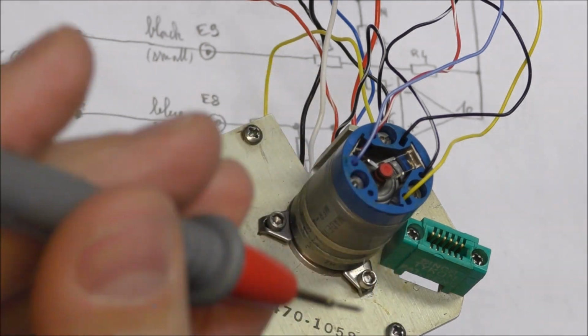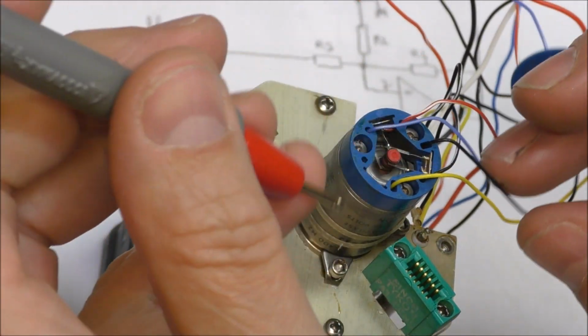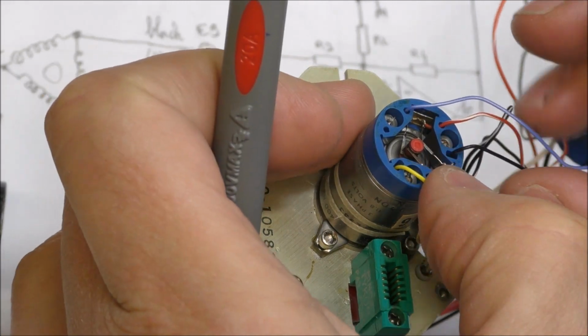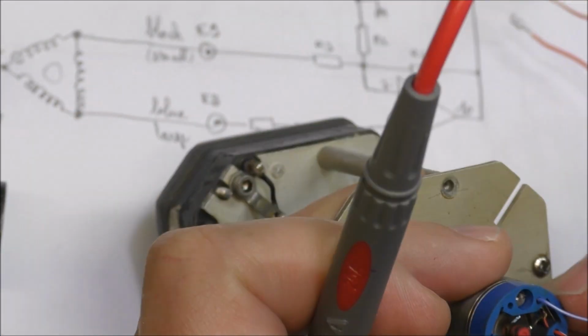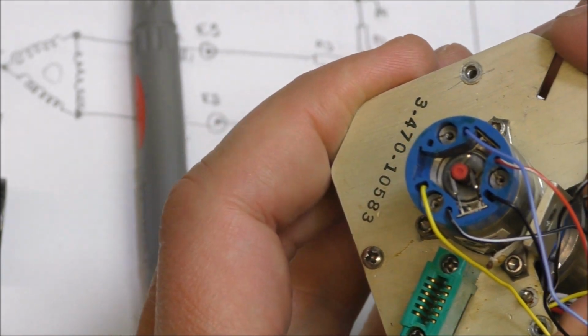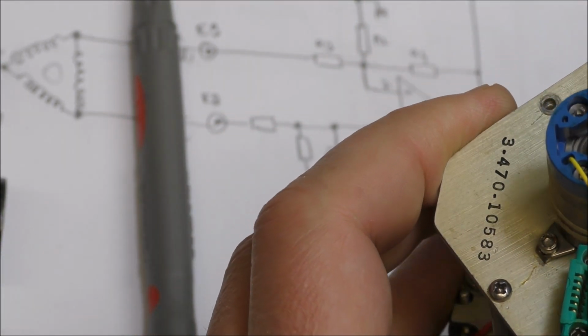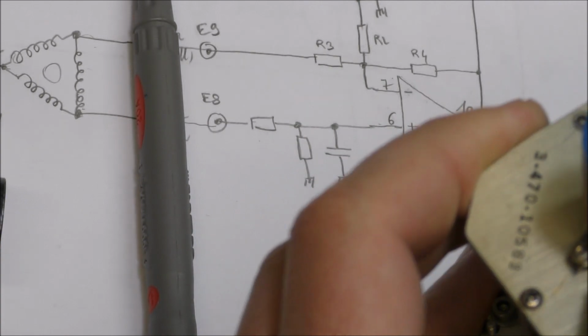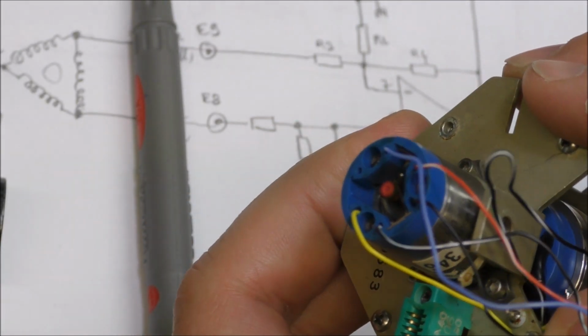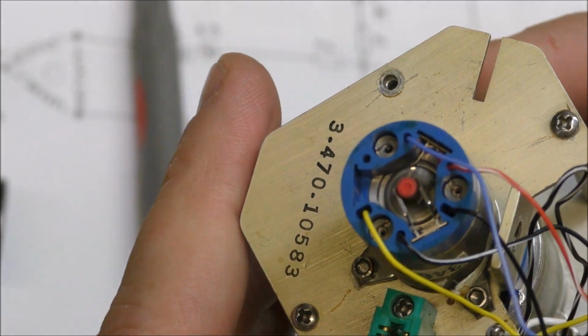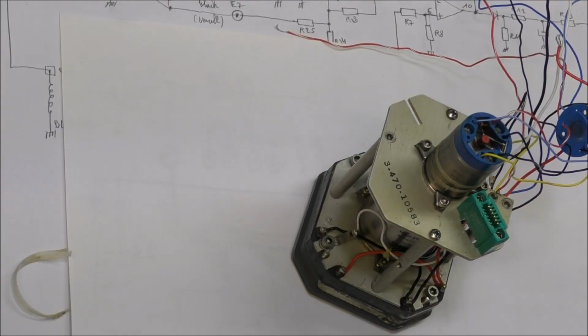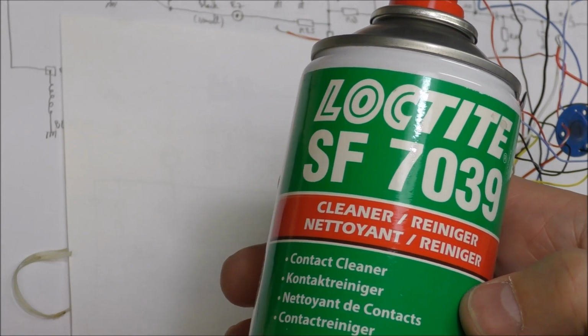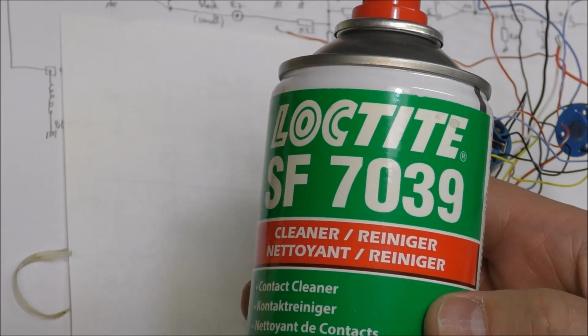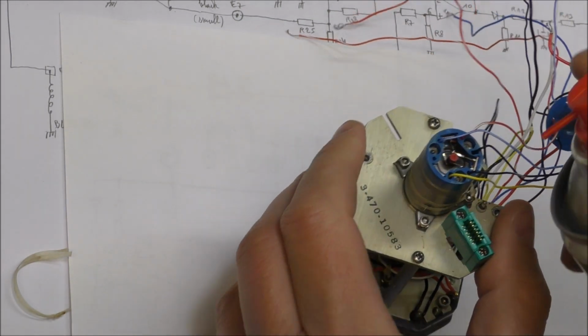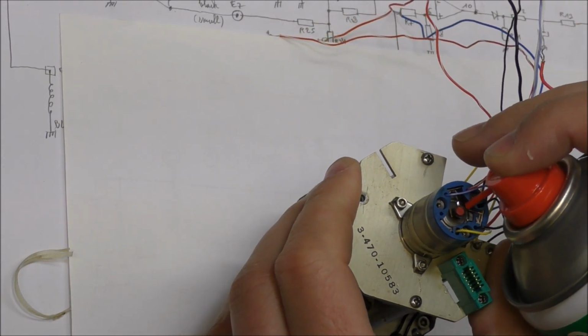So I have an ohm meter here. So normally, so we can see that we have contact in the coil. It seems that the contact is not very clean. Maybe there is effectively a problem, a contact problem. I will try to clean the contact. So I will use this contact cleaning product, Loctite SF7039. I will try. I will inject into this area.